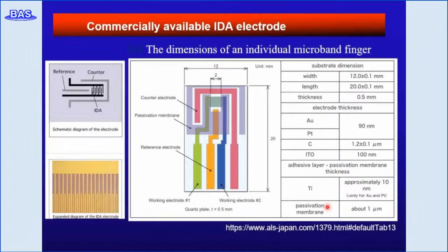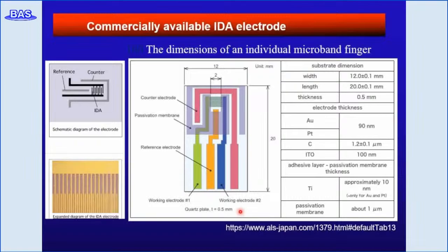This slide shows a commercially available IDA electrode from the ALS catalogue. The dimensions of the individual micro-fingers and available electrode materials are shown here. The reference, counter, and IDA electrode are all printed on one chip plate. Typical dimensions for individual microband fingers are several hundred nanometers in height, 10 micrometers in width, and 5 to 10 millimeters in length. The potential of each finger set of electrodes can be controlled individually.